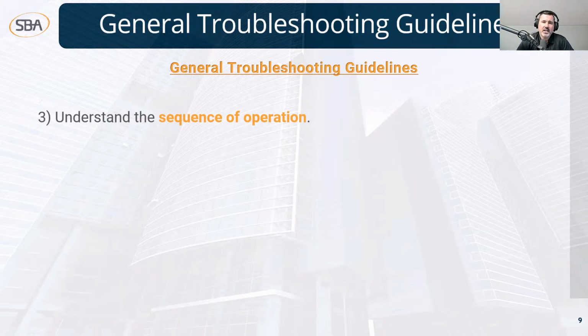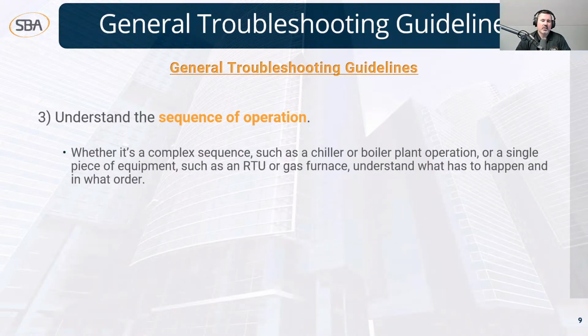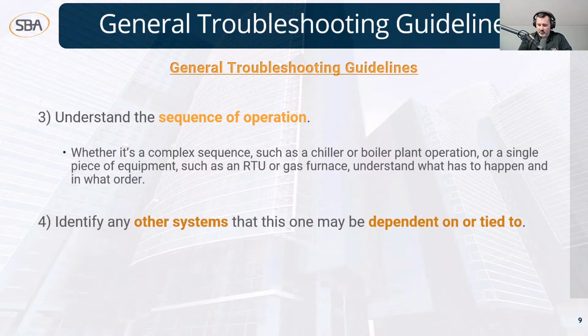Another thing a new hire needs to know: understand the sequence of operation. If you don't know how something is supposed to work, there's no way for you to go and troubleshoot it to see if it's doing what it's supposed to do. Whether it's a complex sequence like a chiller or boiler plant operation, or a single piece of equipment like a gas furnace or a rooftop unit, you need to understand what steps it goes through. You've got to understand what has to happen and in what order to appropriately troubleshoot it.